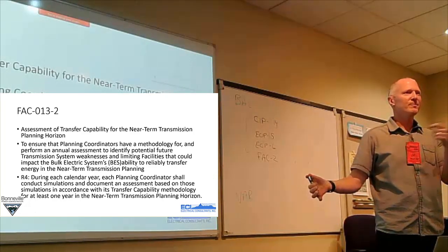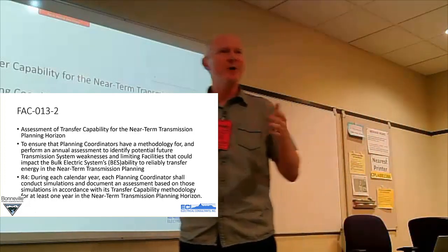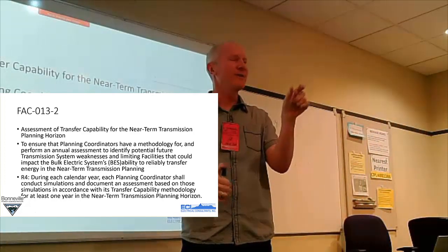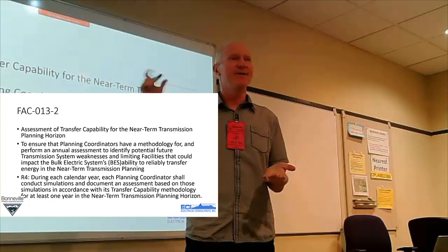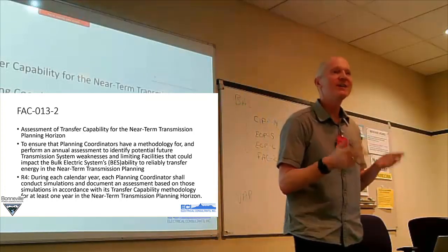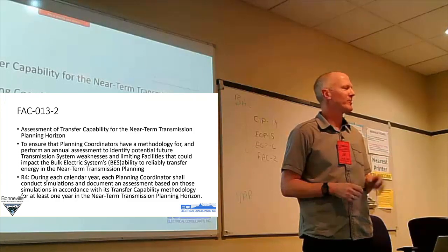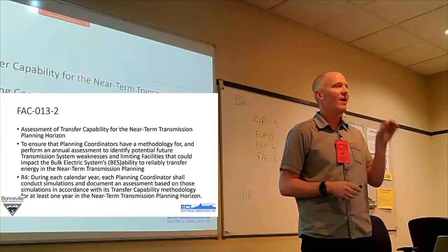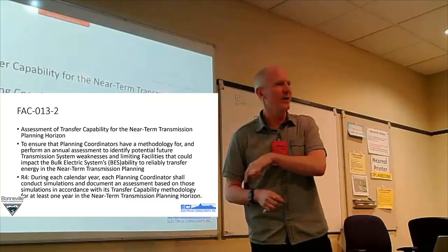Oh, good Lord. Midpoint, Summer Lake. Summer Lake is the one. It's just like it's within a megawatt. So these are tough to do. These are fantastic studies to get a new person in planning. Throw on a FAC 13 study and just wish them well. Because you really have to learn how to balance a case. You will be down there playing with generators that are 10 megawatts just to get the dang path up to its rated flow so that you can run a stability study on it.